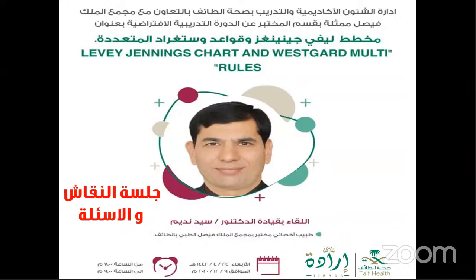Yes, we have two types of errors, as I discussed previously: random and systematic errors. A random error, by the name itself, suggests that it can happen at any time by chance. That doesn't indicate a problem in the system. A random error is only a warning. It can occur due to a bubble in the solution, or during processing there may be a temporary loss of power, or there can be a fading of the lamp for a very, very short duration of time. So random errors are only a warning.